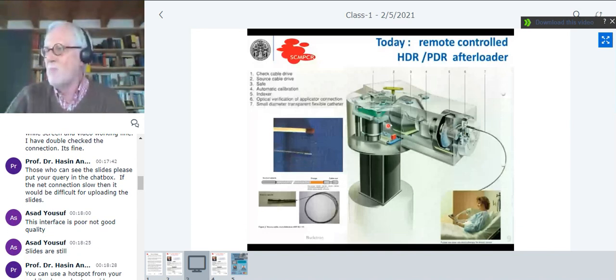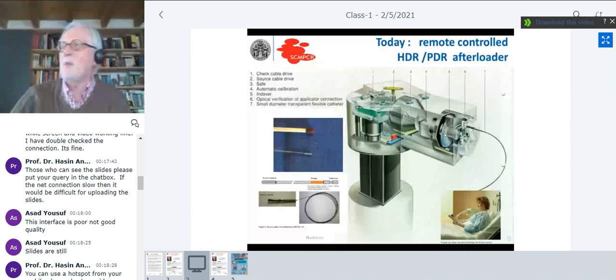What happens is the cable pushes the source out through a system of tubes in here, and it pushes it up to an indexer, to a switch position, where you can serve different channels and have a number of different transfer tubes on there for different applicator channels. It can switch between those, and then you just keep moving it out until it is at the desired position in the patient.